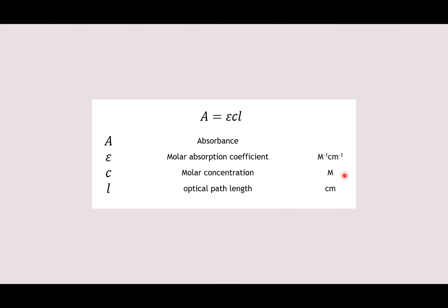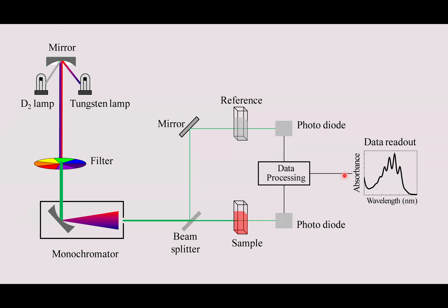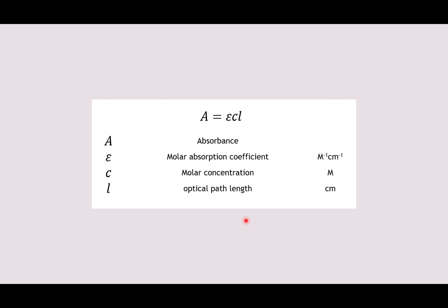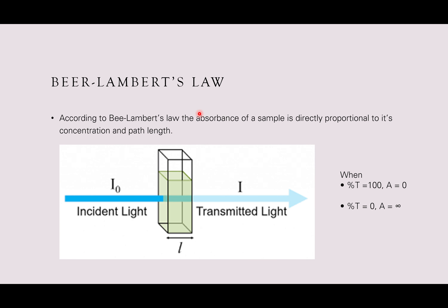A more complex look at a UV spectrometer: we have a deuterium lamp — deuterium being an isotope of hydrogen — that emits light through a filter, filtering out specifically the type of light we want. We then send it through a monochromator to get the specific wavelength we want and shoot this light through a sample. The amount of light absorbed by that molecule is detected. We also use a reference — usually just distilled water — to confirm the spectrometer is working. From the reference and sample data, we get a graph we can analyze.